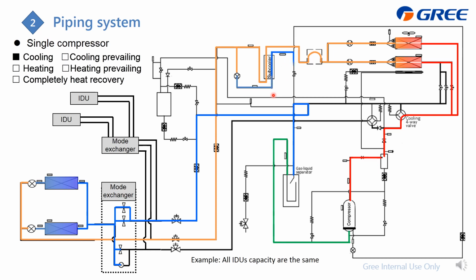And also similar to the heat pump, this part is for the subcooler. A partial refrigerant will get through this subcooler EXV, and then cool the rest down more, to increase the subcooling, and itself will become gas and then flow back to the gas liquid separator.